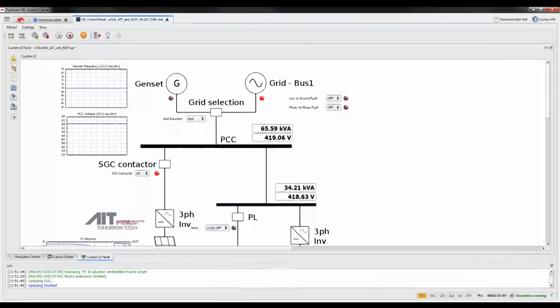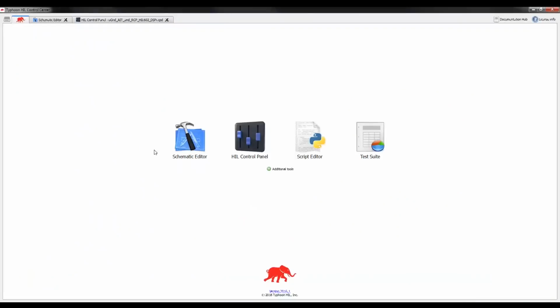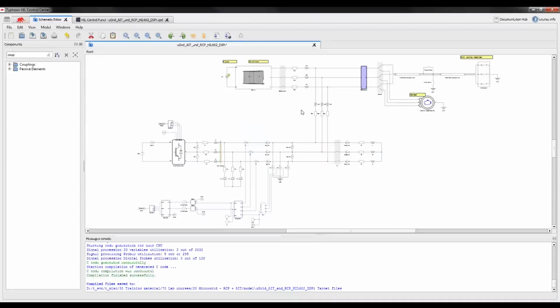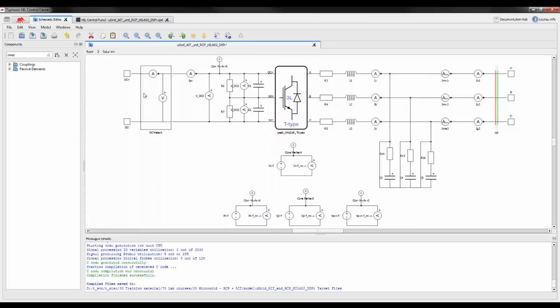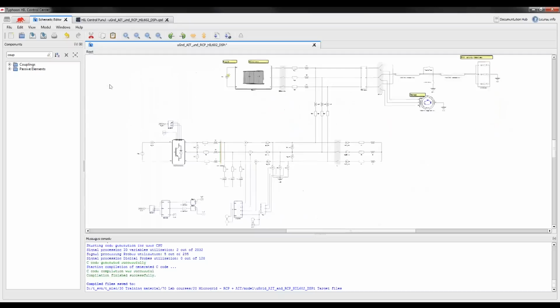real-time simulation environment. For those of you that are not familiar with our environment, it consists of 4 key blocks: schematic editor, control panel, script editor, and test suite. We'll start with the schematic editor, which is how you specify the schematic that you're trying to simulate in real time. And this is the microgrid that we are simulating, the one that you just saw the one-line diagram of. What is really interesting is that here you have a solar inverter. That's the one that is controlled by the AIT controller. And if you look inside, you're seeing a complete power stage with the filter embedded inside the inverter block, so you can clearly see the multi-level schematic feature.